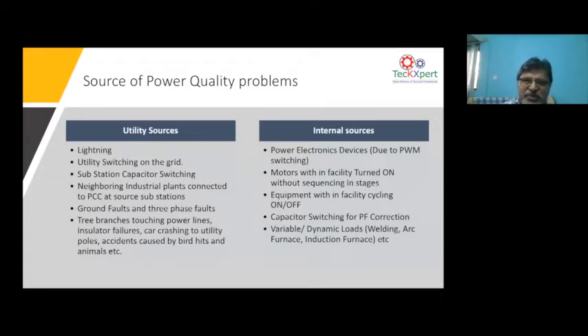In the BESCOM network, if a ground fault or a three-phase fault happens, it can create a voltage sag or a swell. So that also can be an externally generated power quality problem. Tree branches touching power lines are a common issue in Bangalore. There are also insulation failures, because sometimes an insulator on a power line can deteriorate over a period of time and fail, and it can create a voltage sag or a swell. So these are all utility related power quality problems.